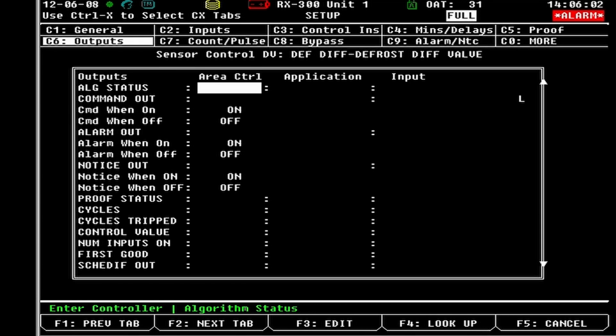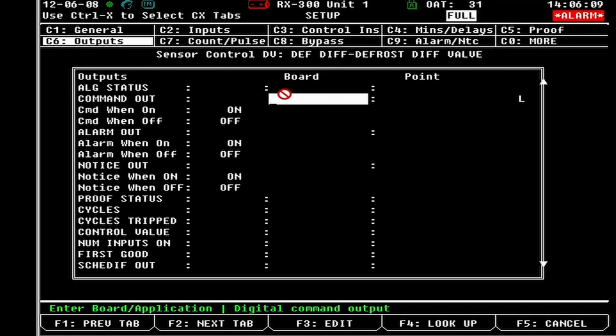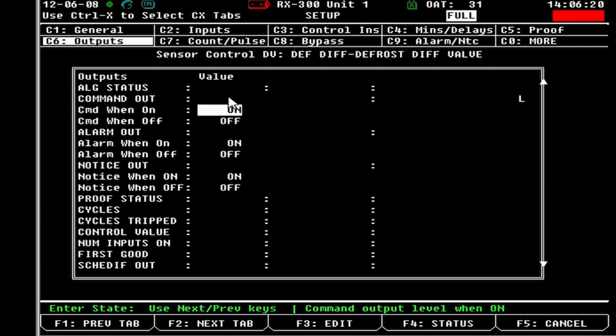So again, in here on the outputs, you have your command out. So that's going to be where you tie your board point to, just like in the analog sensor control. And then in here, command when on. So you could change this. So when the control value is on, you could change this to off. When the control value is off, you could change it to on.